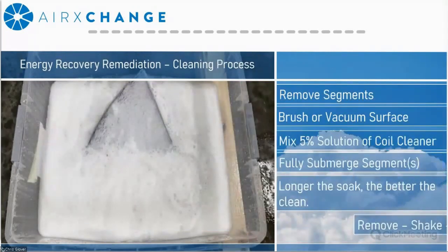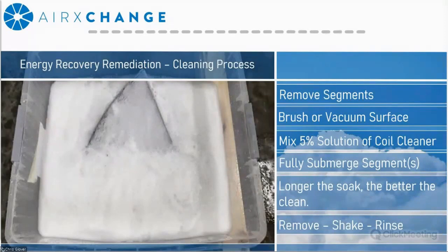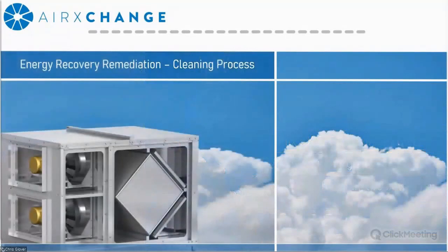So once you remove the energy transfer segments, the process of cleaning is pretty straightforward. You're going to want to brush or vacuum the surface area just to get any excess residue off the surface. You're going to mix a solution of coil cleaner or detergent in the bucket, and once again, fully submerge that segment in the water. This is going to allow you to get that good deep clean. In general, the longer you can let these things soak, usually the better the clean is going to be. This could be anywhere from a couple of seconds to a couple of minutes to a couple of hours, depending upon how dirty they are. Then after they're done soaking, remove them and rinse them off with just non-pressurized tap water. I should say, shake them off pretty vigorously so you remove any excess water, then put them back into the unit.